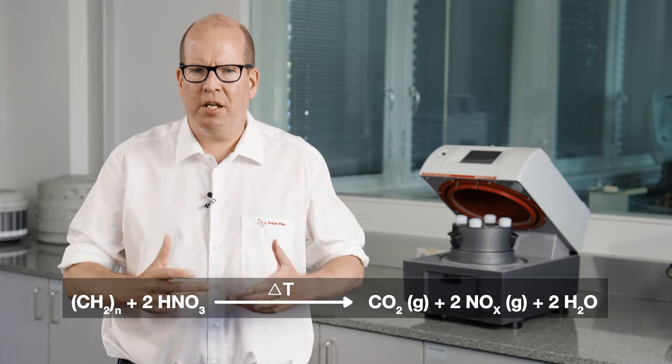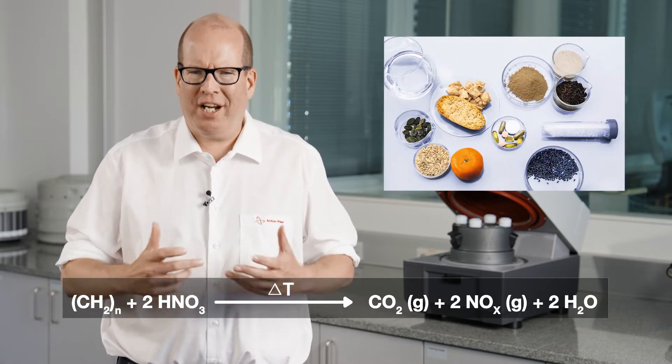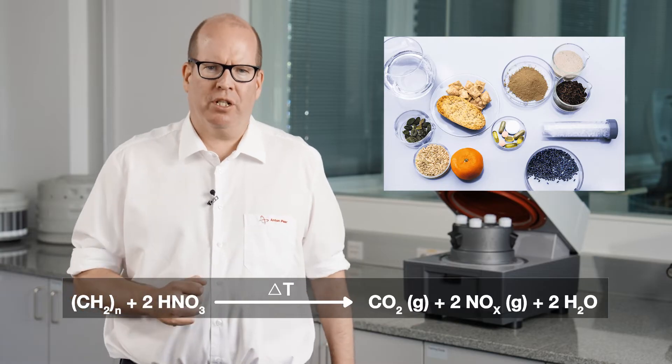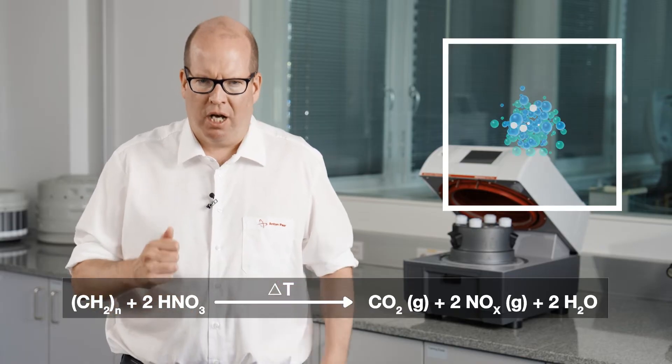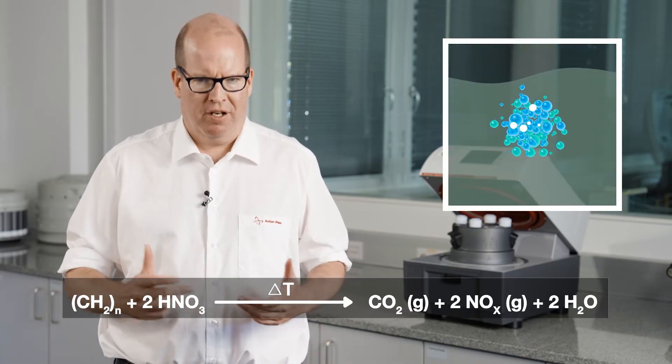Let's look at the chemistry. What actually happens when we add acid to an organic sample? The acid, usually nitric acid, oxidizes and decomposes — that is to say digests — organic matter such as food, pharmaceuticals, polymers, and petro samples. As a result, carbon dioxide and nitrous gases are formed. Trace elements that the sample might contain remain in solution, while the main components are destroyed.